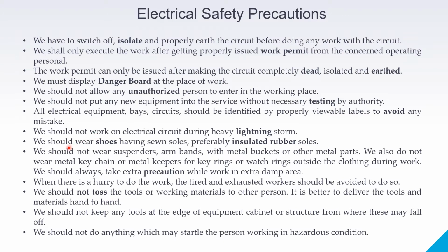We should wear shoes having sewn soles, preferably insulated rubber soles. We should not wear suspenders, armbands with metal buckles or any other metallic parts. We also do not wear metal keychains or metal keepers for key rings or watch rings outside the clothing during work. We should always take extra precaution while working in extra damp areas.